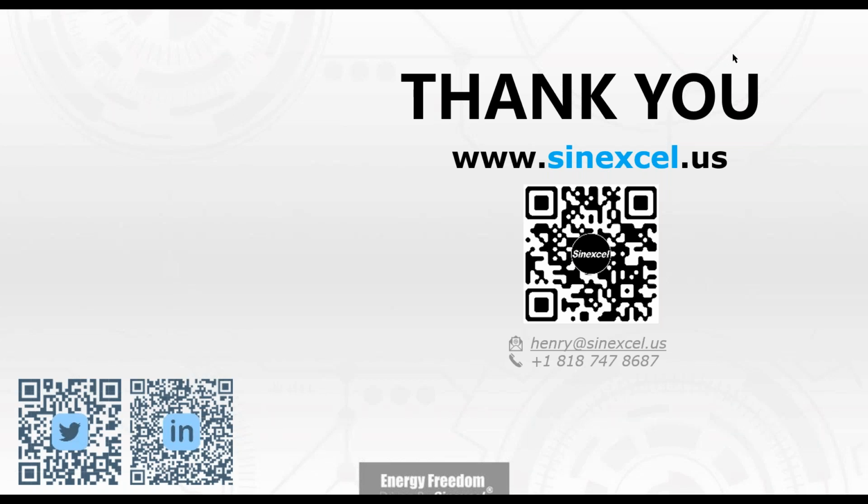For the second part, Marty mentioned grid forming to grid following. I know there are quite a lot of customers who would like to know if the ESS could replace the UPS. Frankly speaking, I think that is quite challenging, but we do have a solution: the smart transfer switch that I mentioned. With that equipment, we can get it done within 200 milliseconds, almost within several cycles, to get back to power supply. So I would say it can cover most UPS requirements, so it is perfectly good for UPS extension. That's all.